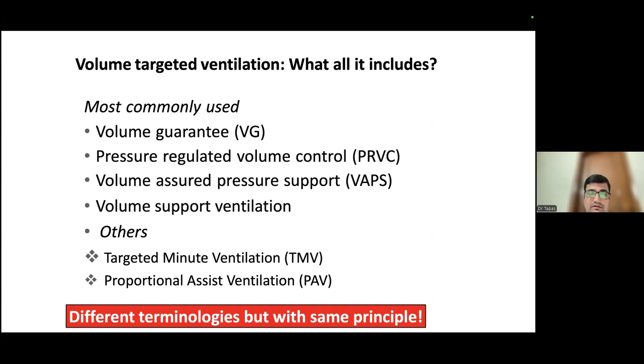The ventilator will measure the exhaled tidal volume of the previous breath, then compare it with the set tidal volume, and if the delivered tidal volume is less than the set tidal volume, it will increase the working pressure in the subsequent breath, so that the delivered tidal volume matches the set tidal volume, and so on.